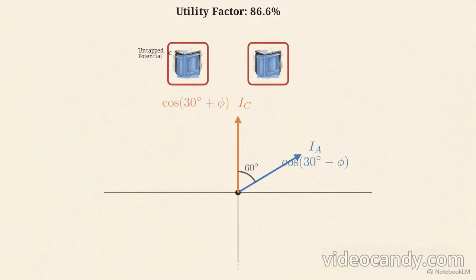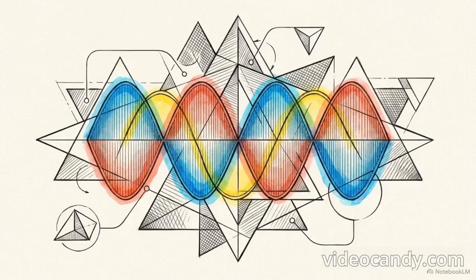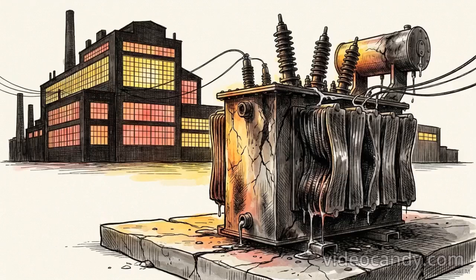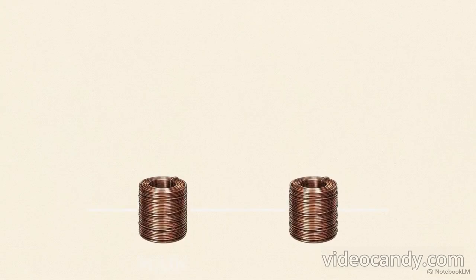Look at the lower phasor diagram here. Notice the asymmetrical angles of the current vectors. In an open delta setup supplying a balanced load, one transformer operates at a power factor of cosine(30 minus phi), while the other runs at cosine(30 plus phi). This proves that 3-phase power does not physically require 3 coils. It relies on relative vector geometry, allowing the system to keep running in an emergency, but at a severe mechanical efficiency cost.